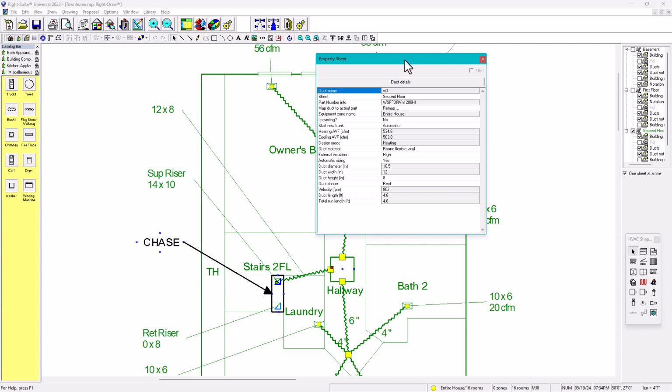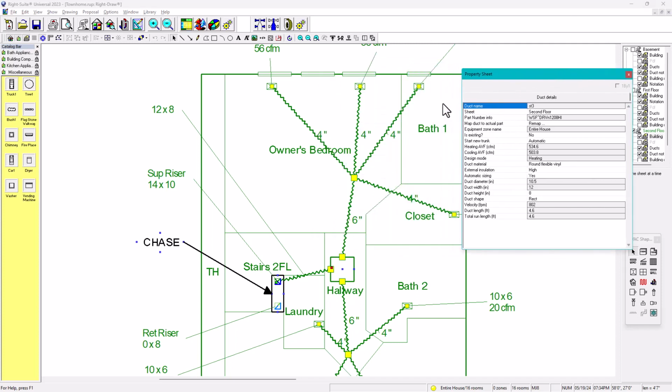But now it's interesting because since we're in the attic, it shows a lot of ducts that are flexible, right? These are all flex ducts, and all of them are round. Flexible ducts give you more flexibility, but you have to be careful with installation too. You don't want to have a lot of sags, or squish those flex ducts. It has to be as straight as possible, right? But in this case, since all of them are round, I'm not going to put in here rectangular, rigid. So we're going to continue with the flex duct, okay?